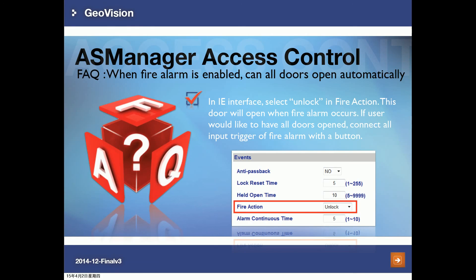For the FAQ section: when a fire alarm is enabled, can all doors open automatically? Yes. In the controller's web UI, go to the fire section under Events and select Unlocked. This way all doors will open when a fire alarm occurs. If you want every door to open when a fire alarm is triggered, you can connect all fire alarm input triggers with a button so pressing the button opens all doors simultaneously.